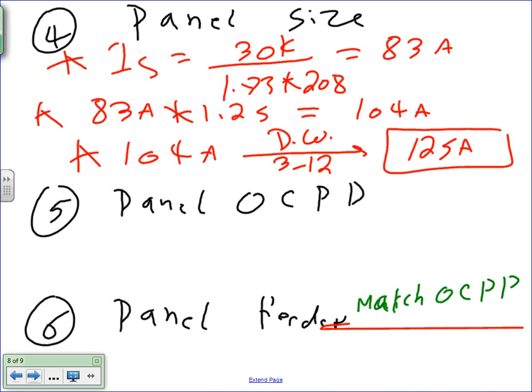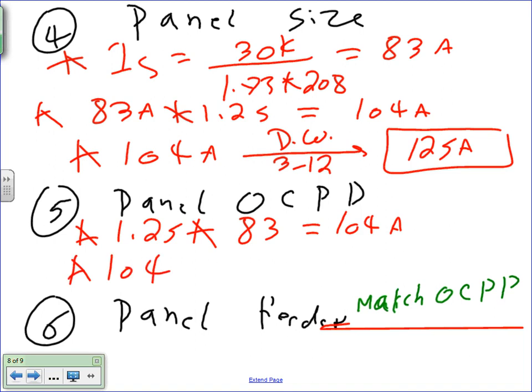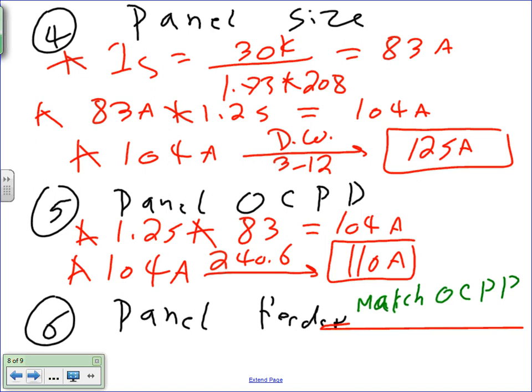Okay, 125. For the overcurrent protection device, the same calculation: I take the 1.25, assuming it's continuous load, 83 amps gives me 104 amps. Where do we take it to find the overcurrent protection device sizes? 240.6, and the next standard is 110. Yeah, 110 amp.